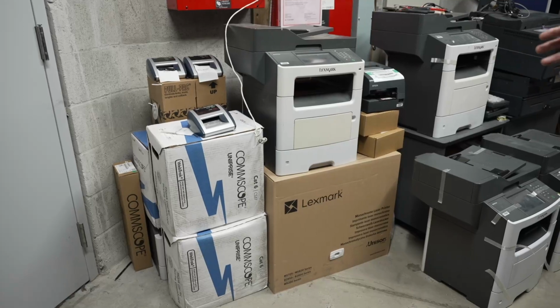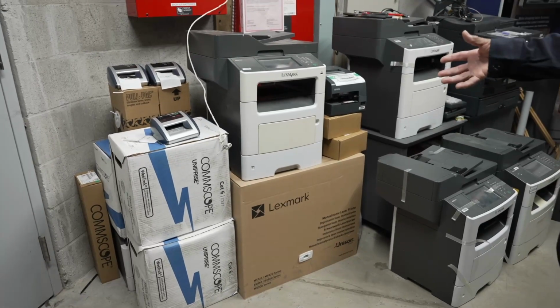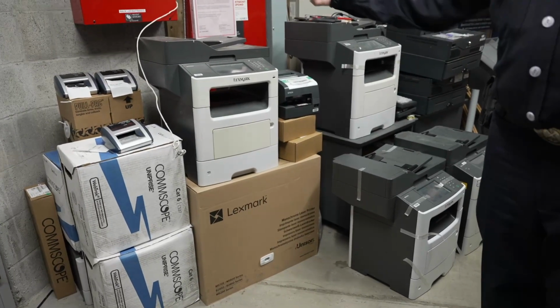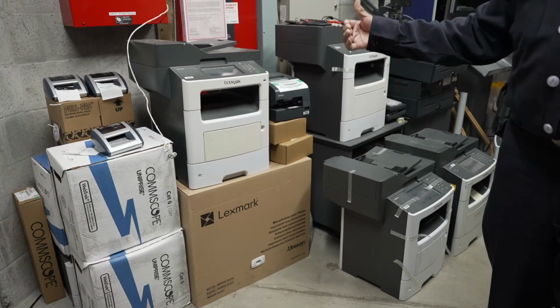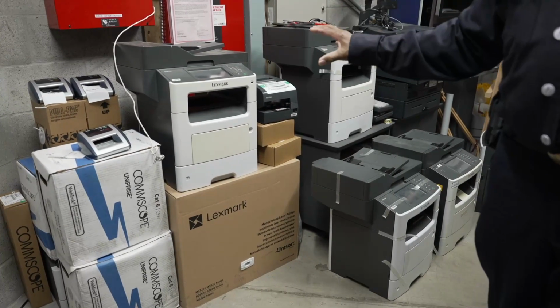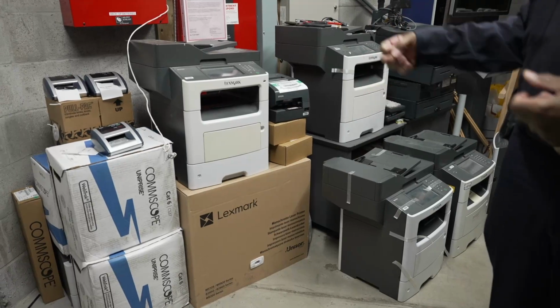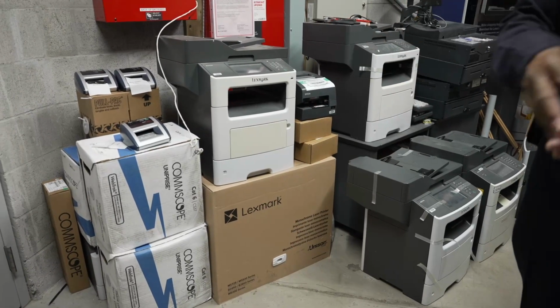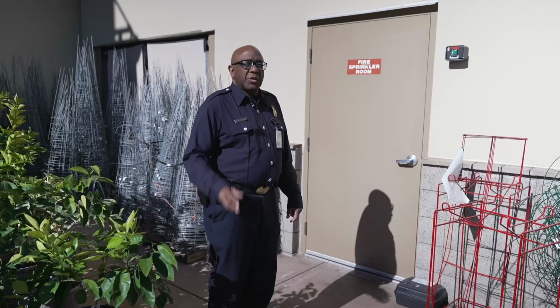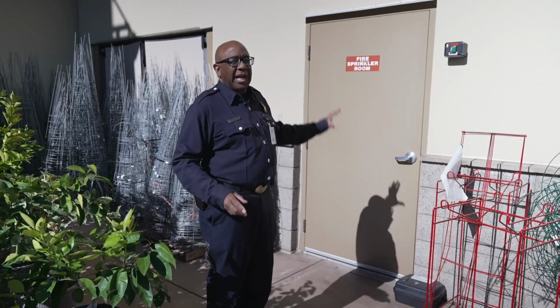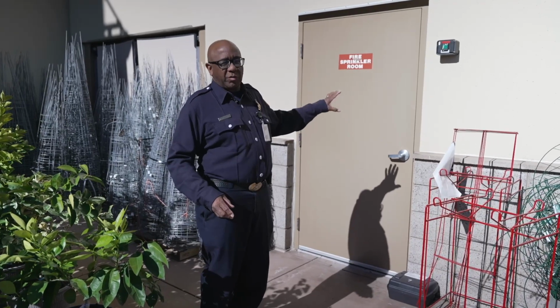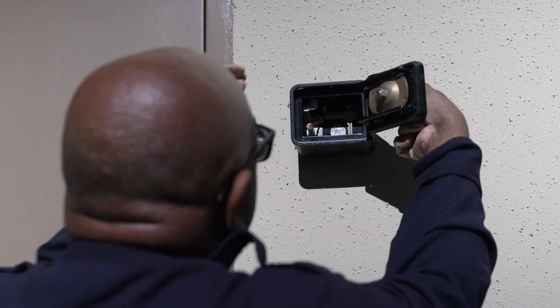So now we have a violation of the electrical code. You're supposed to keep clear in front of the panel for 30 inches, and that has not been done here. This is an easy to fix violation. They can probably do it while you're still in the store. So many of the large big box stores are going to have a separate fire sprinkler riser room. You're going to access that using your Knox box key and enter that room.